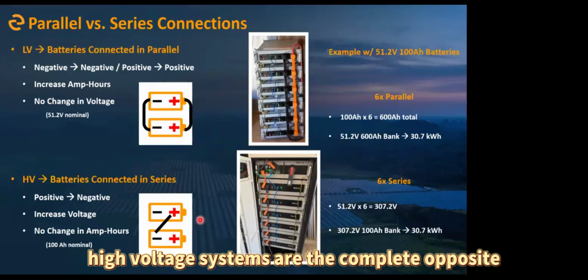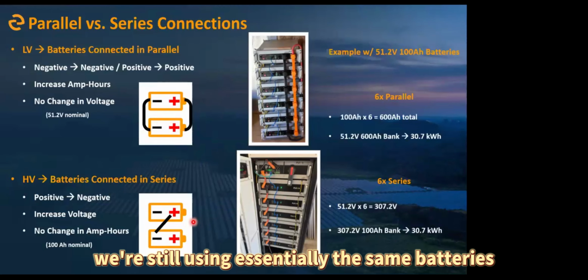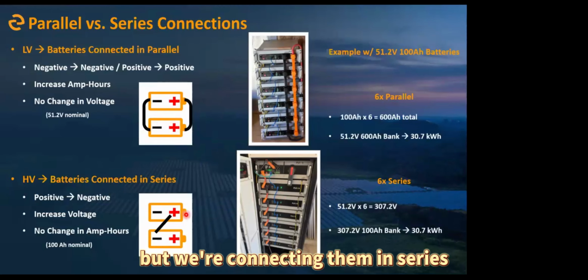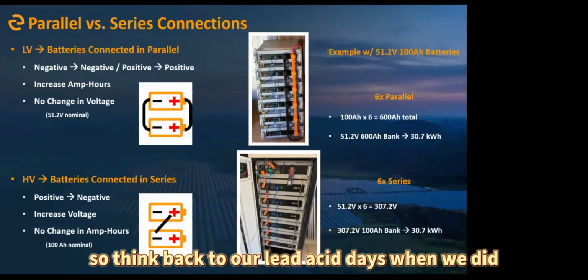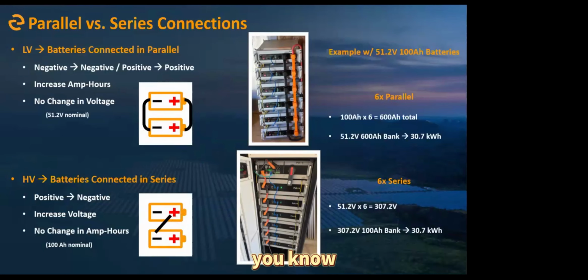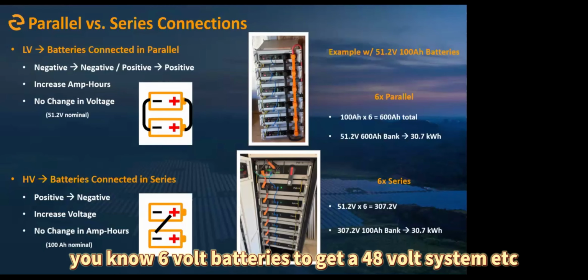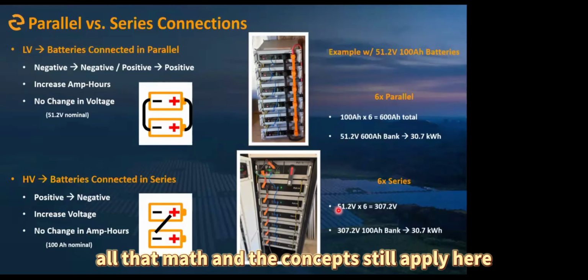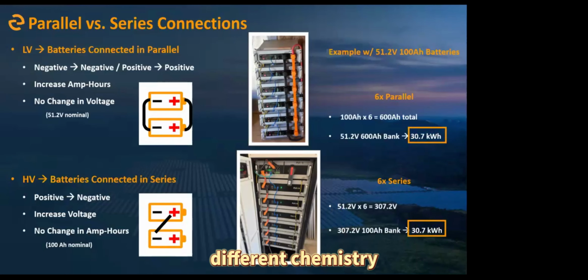High voltage systems are the complete opposite. We're still using essentially the same batteries, but connecting them in series, positive to negative, instead of in parallel. Think back to our lead acid days when we did two strings of 8, 6-volt batteries to get a 48-volt system, etc. All that math and the concepts still apply here - we're just talking about essentially different chemistry.